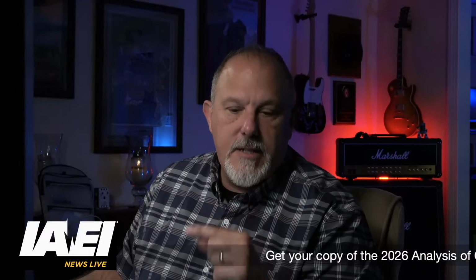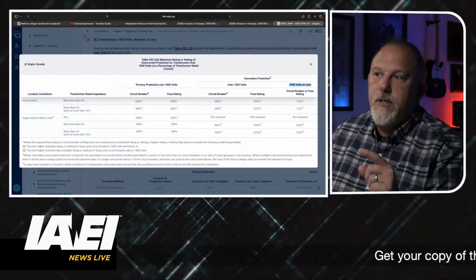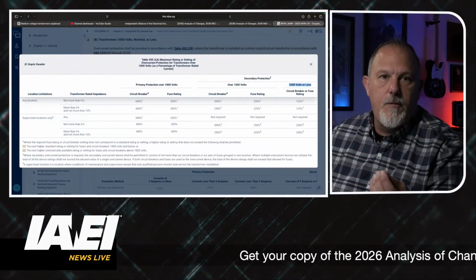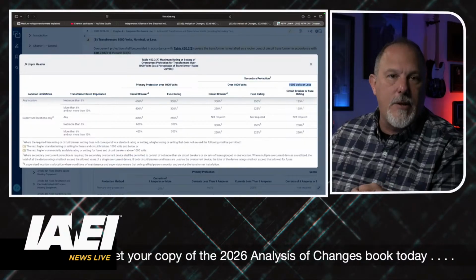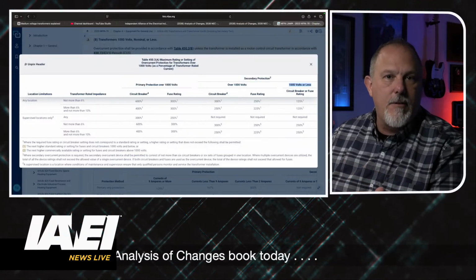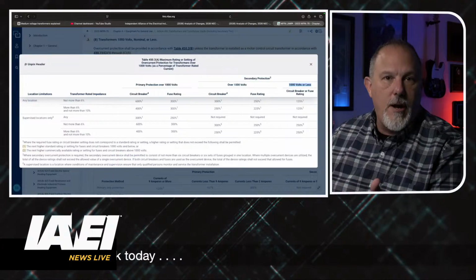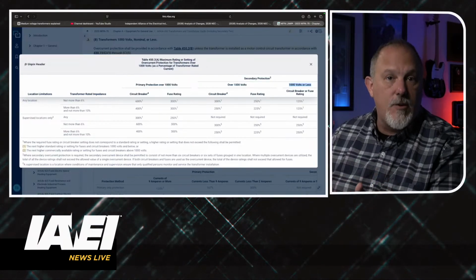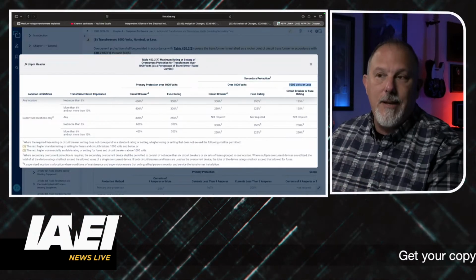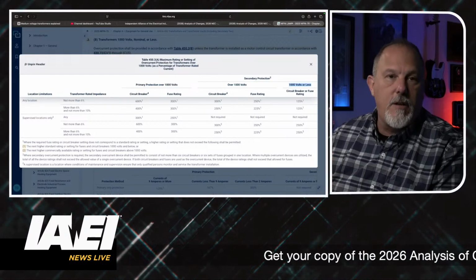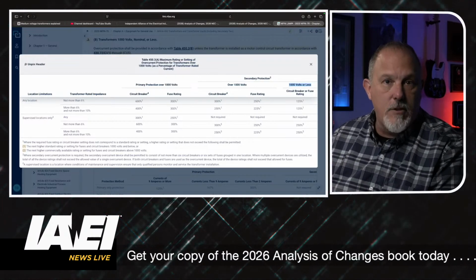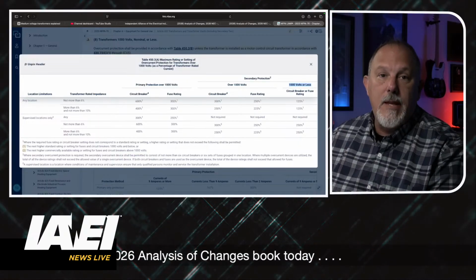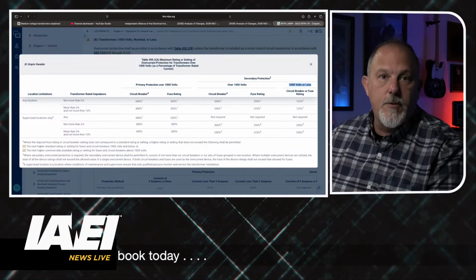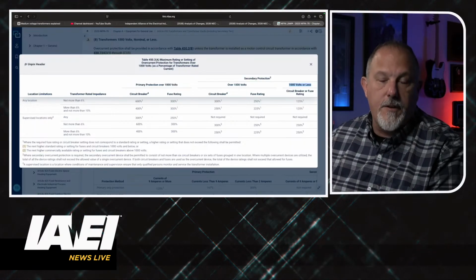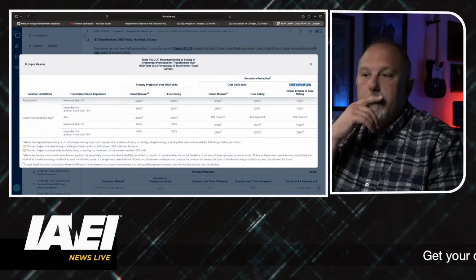But in any case, this table is giving me the option to go when my secondary is less than or equal to 1,000 volts. And that's the indicator that regardless of whether or not you have a low voltage side to a transformer, you are still in table 450.3a. Even though one side is medium voltage and the other is not, the entire transformer is covered under 450.3a.